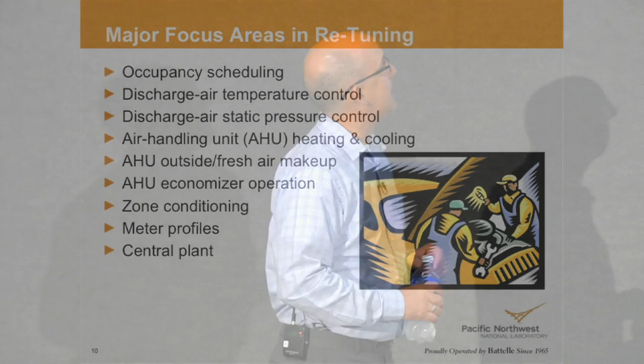Temperature control, static pressure control, heating and cooling - we find a lot of heating and cooling simultaneously occurring. They mask each other. The end result is we get the proper temperature coming out of the diffusers in the ceiling, and occupants in the space are happy, but what's going on? Why are we heating and cooling at the same time? Are we even aware of it?